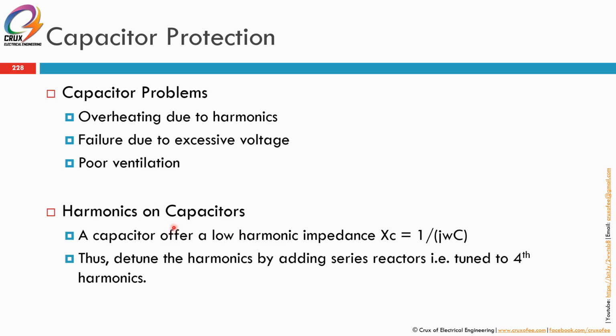So, harmonics on capacitors. If you are using a capacitor bank in a system with a lot of harmonic equipment such as VSDs, variable speed drives, UPS, uninterruptible power supply, or any static VAR compensators, these harmonics can affect the capacitors. A capacitor offers a low harmonic impedance. This is the impedance of the capacitor: Xc equals 1 over j omega C.